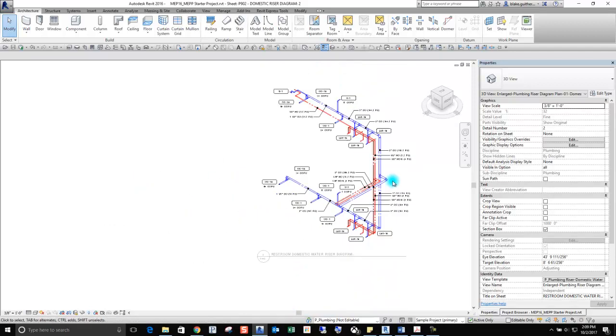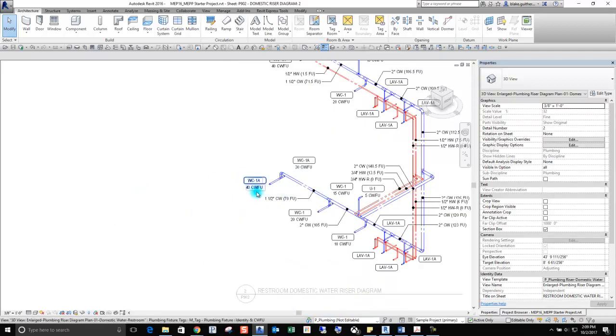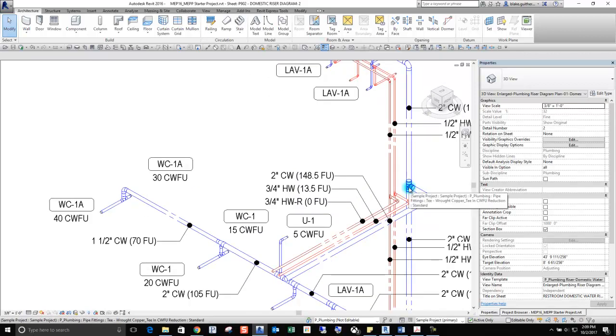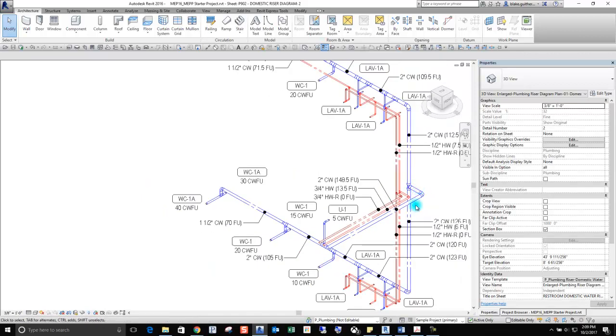So with a very big building, each branch is going to have to be sized with these overrides if you follow Chapter 6 in the UPC. And then wherever you have a T here, you're going to apply that diversity reduction so that your piping system doesn't have all those overrides included in the entire system.